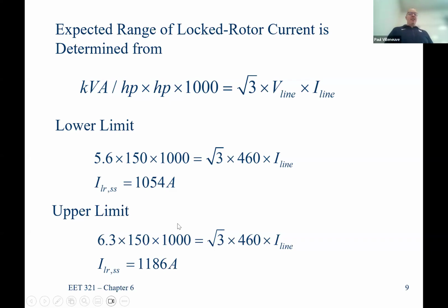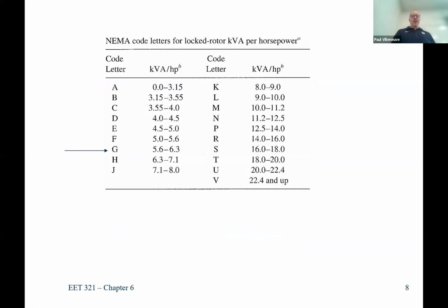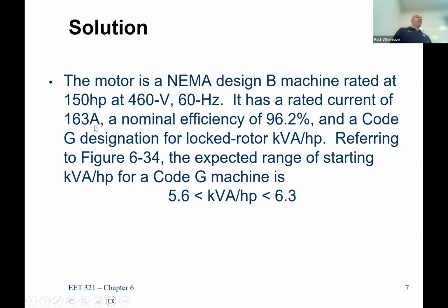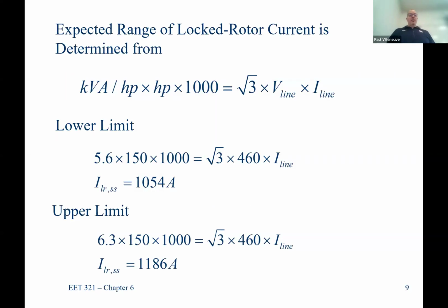So in the application that we saw, that 150 horsepower, even though it pulls 163 amps at full load, at the lower limit for where it starts, it pulls over 1,000 amps, 1,054 amps. When it starts, that's a low range. At the high range, it's almost 1,200 amps. And that's perfectly fine. That's what the motor requires to operate efficiently and effectively, to at least get started. Once it's started, then it's different. Transformers also operate like this. Any consistency between transformers and motors, induction motors?